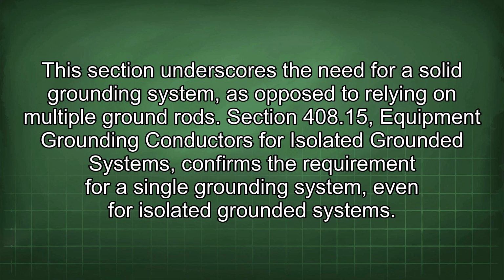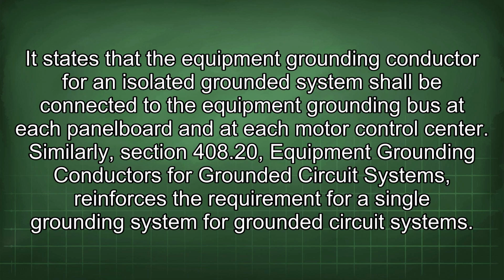Section 408.15, Equipment Grounding Conductors for Isolated Grounded Systems, confirms the requirement for a single grounding system, even for isolated grounded systems. It states that the equipment grounding conductor for an isolated grounded system shall be connected to the equipment grounding bus at each panel board and at each motor control center.